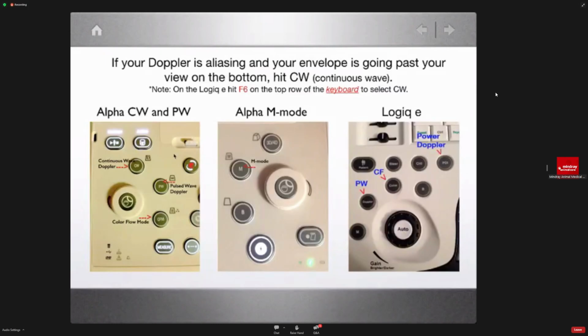Now, Doppler, there are 3 settings on Doppler. One is color flow, or CF here. Power Doppler we don't use typically in echocardiograms, but we do in the abdomen. And this doesn't give you direction, it just tells you if there's blood flow, and it's much more sensitive than color flow, just to know what power Doppler is. But for echocardiogram purposes, we want color flow first, then the PW, and then on the Logiq E, F6 is the CW.